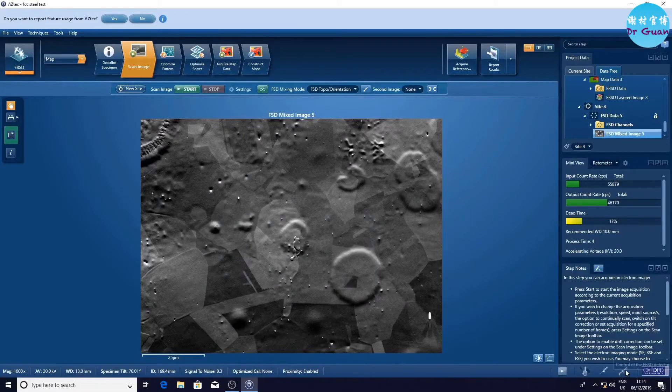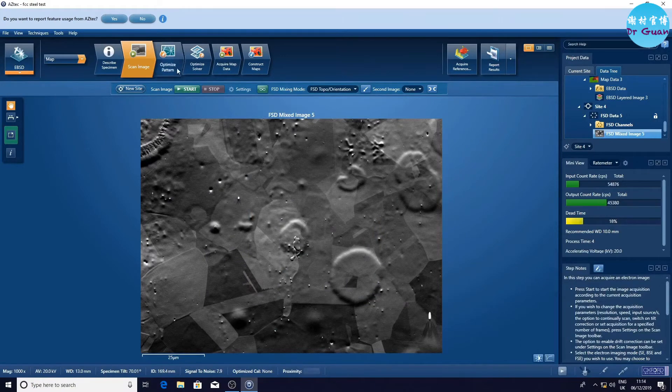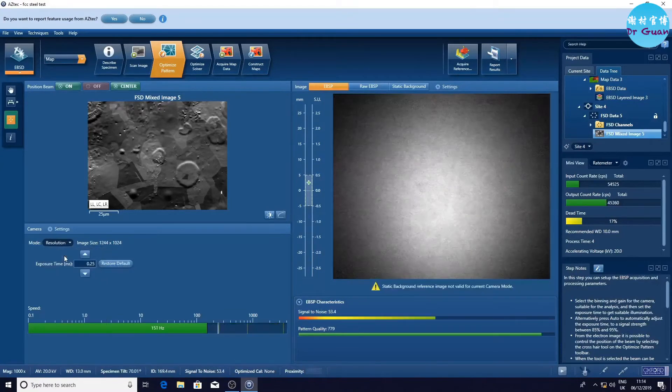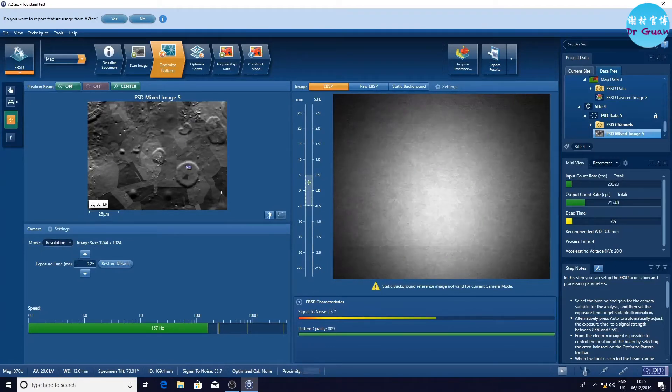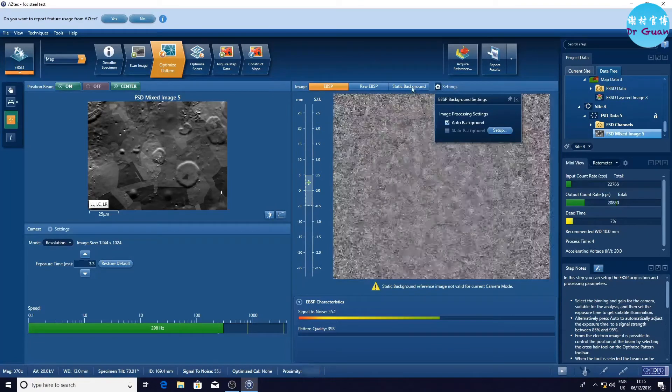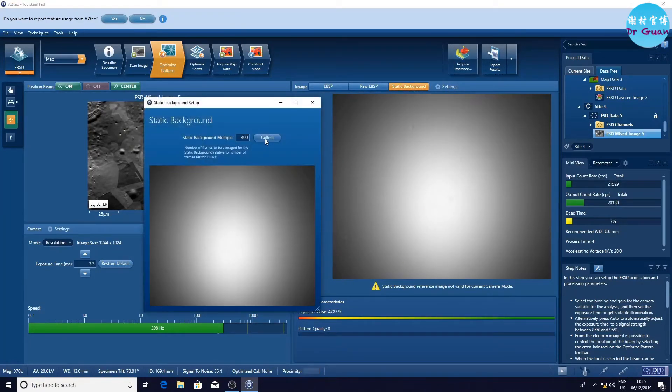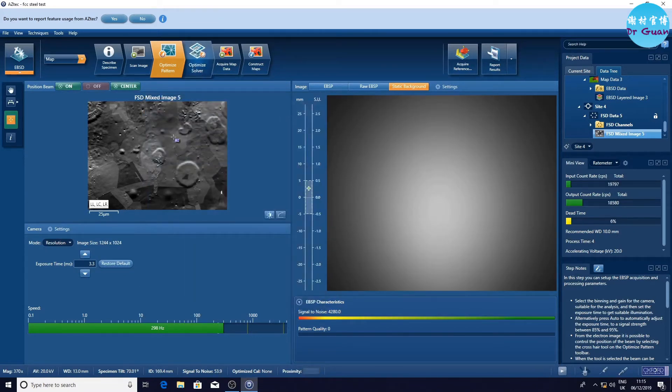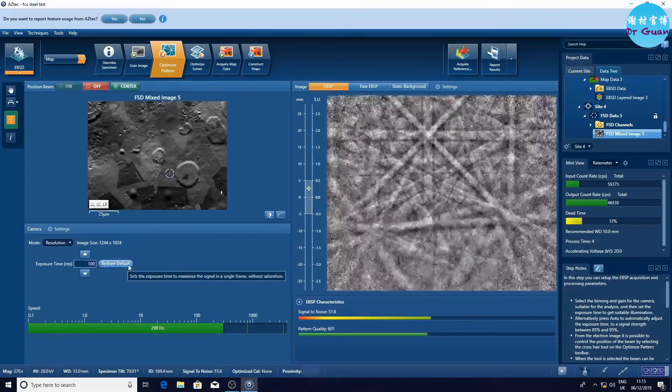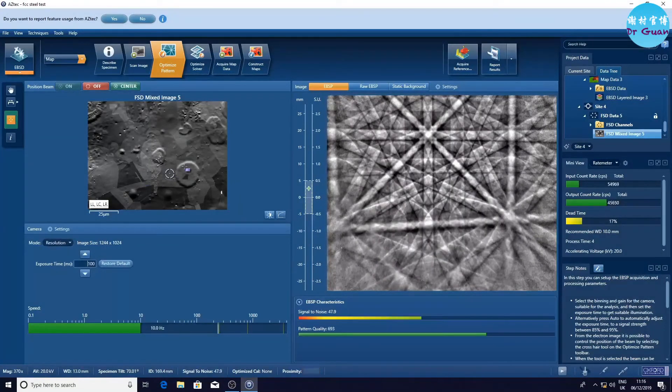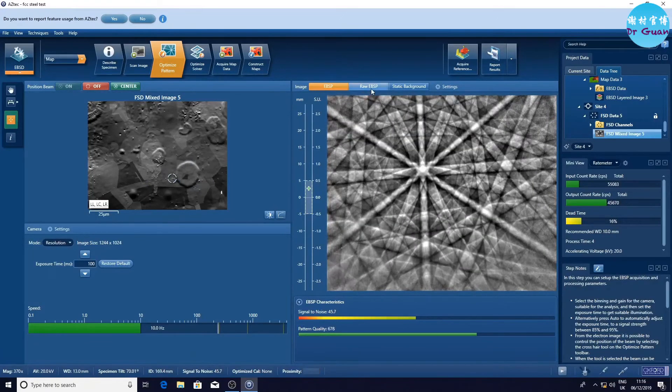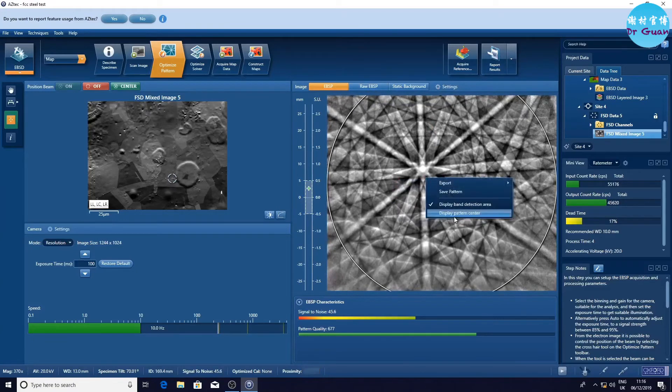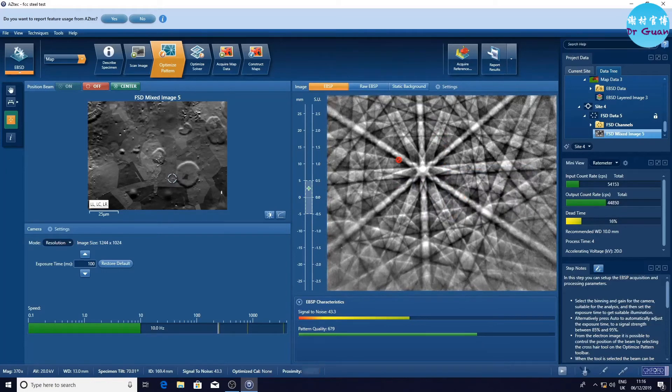Now we're going to do the high resolution EBSD analysis. How can we collect the high quality EBSD Kikuchi patterns? Definitely, we are going to choose the resolution mode. Then we can use the restore default to determine the exposure time, so now it's 3.3. We need to check the static background. Now it's not working. Collect the static background, normally 400 multiple. Then we can see the Kikuchi pattern is not very good quality. So we increase the exposure time to 1000. Now it gives you nice Kikuchi patterns. We can display the detecting area and the pattern center.